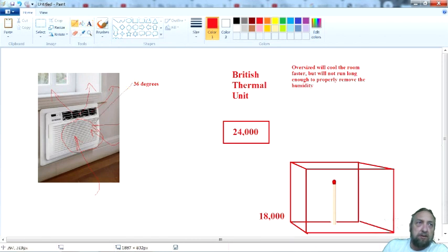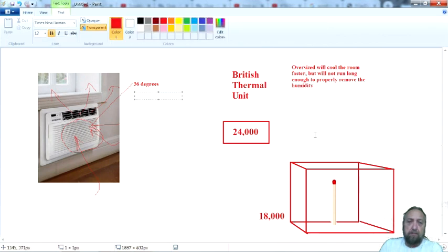Let me just go down here. So this evaporator is running about 36 degrees. So if it's not going to frost, what would you see at about 36 degrees on the evaporator? Moisture? Very good. You'd see moisture. It would be cold and wet. Now this is important, and this is what I'm leading up to: what do you tell the customer when the customer says it's not cooling?